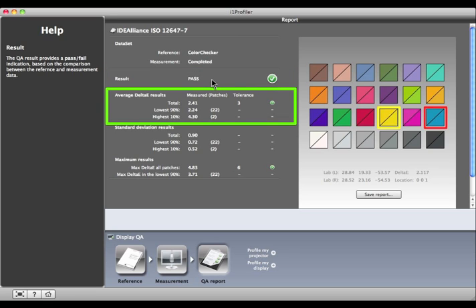Here are the average Delta E results. The average Delta E of all of the measured patches is 2.41. Since the tolerance is 3, we are within tolerance.